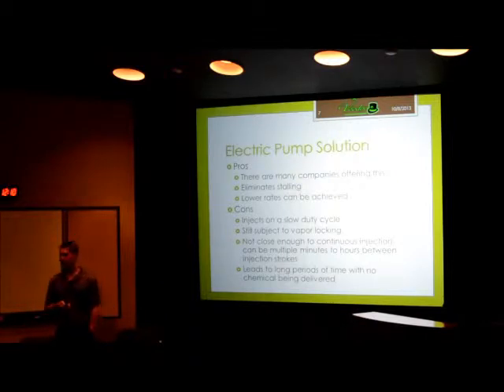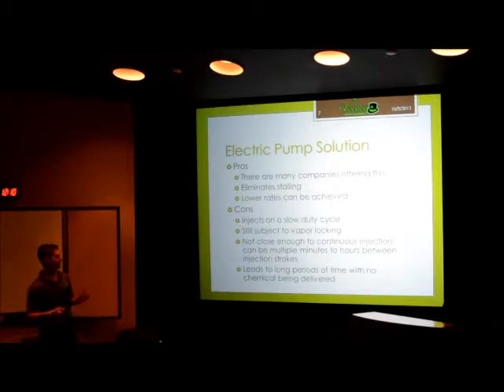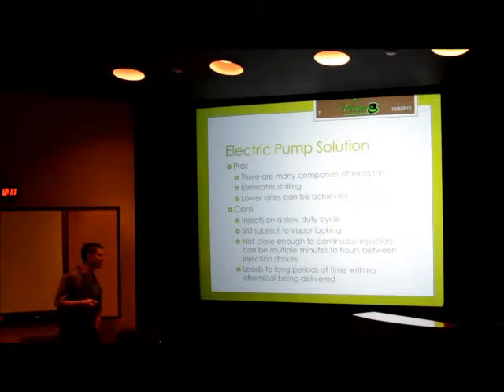very slow. I've seen some of these pumps where they slow it down, it almost works on a screw type. So to get that liter a day, it takes up to 15 minutes to do 1 stroke and then return, and then another 15 minutes. So you can imagine with this viscous chemical, especially with temperature changes, you're not even displacing it from the tank to the pump. You're going to run into problems with vapor locking. You're just moving the chemical very slow. Methanol is not so bad. Other chemicals are still subject to vapor locking. You're not changing anything. You're moving everything so slow.